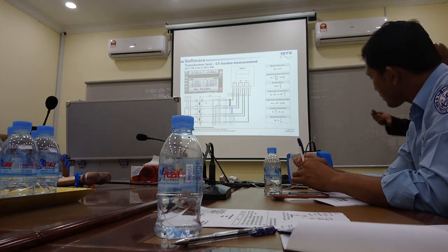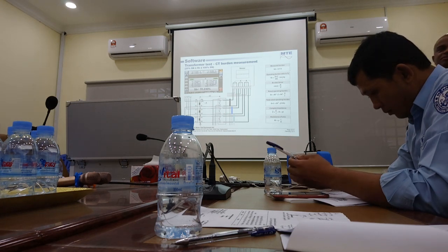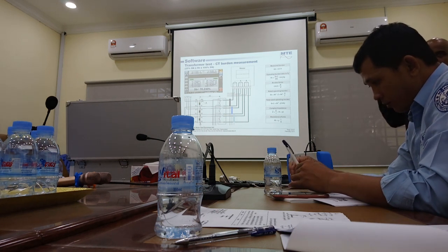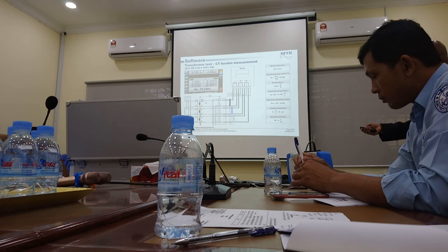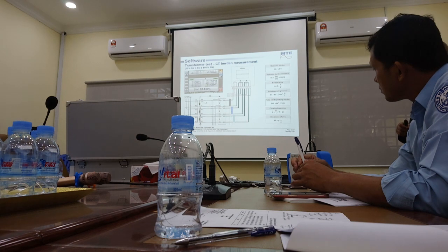Okay? That is why, if you remember, in the first presentation I showed today, you saw 20 millivolt to 300 volt. You may ask why you need 20 millivolt in the power industry. Only for this reason. Because only in channel A, that means phase 1 voltage, that channel alone can measure very low millivolt like in a multimeter. Because you are talking about checking the wire resistance by passing a current through it. Okay? So that is CT burden measurement.